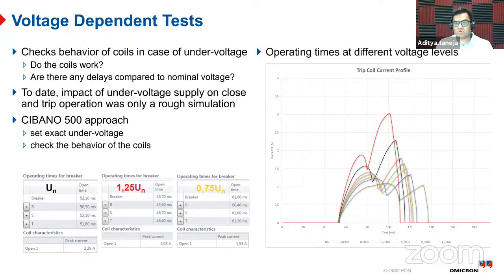doing this test has shown us faulty coils, or not faulty, because they were working fine. Customers have told us that this breaker is working as normally as any other breaker, but when we did the test, it did not operate, or it operated with a lot of difference compared to the other phases, and it was a clear indication for the operators to replace it before that breaker creates a problem in the network for them. So, yeah, one key takeaway here.